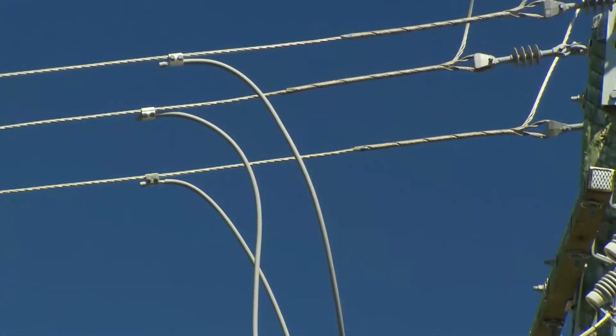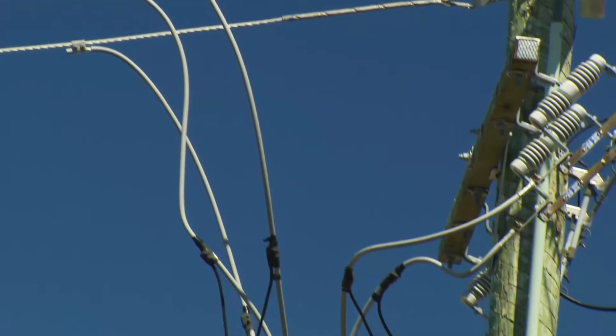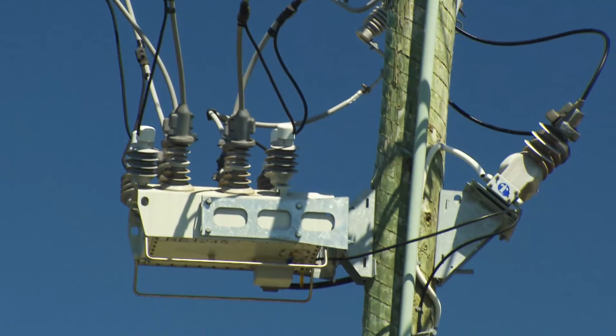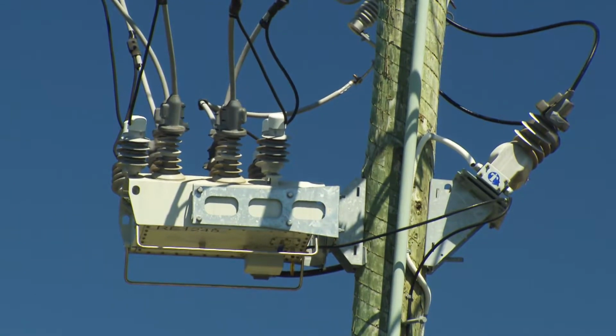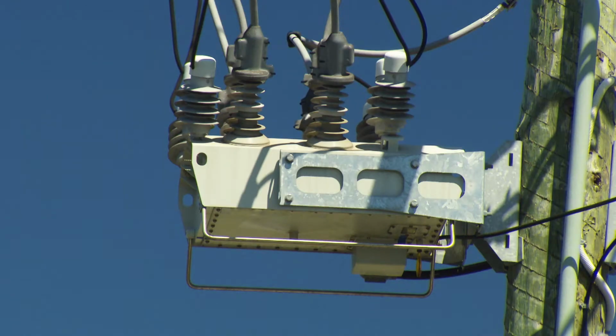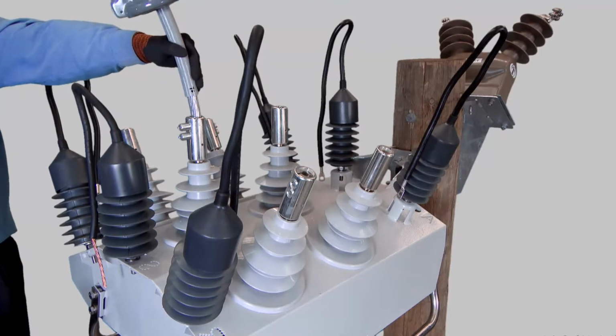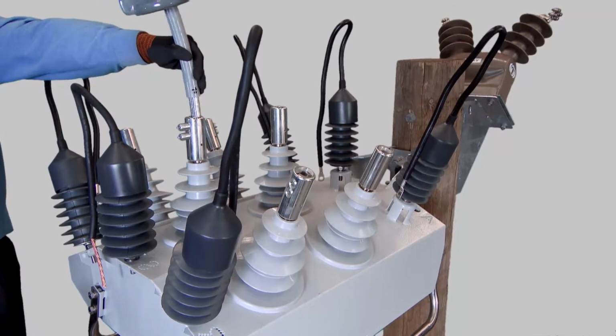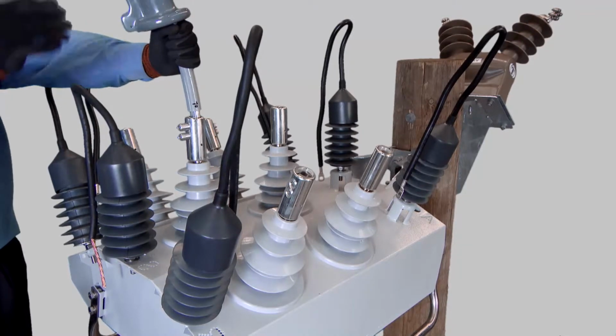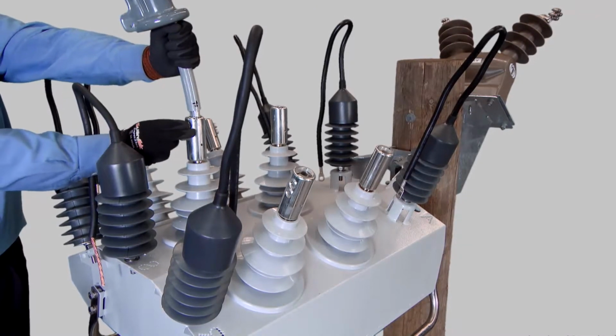NOJA Power recommends that all high voltage connections are done using insulated high voltage cables and bird guards. This will protect the tank from short circuits caused by animals and will make it easier to keep acceptable clearances in the installation.